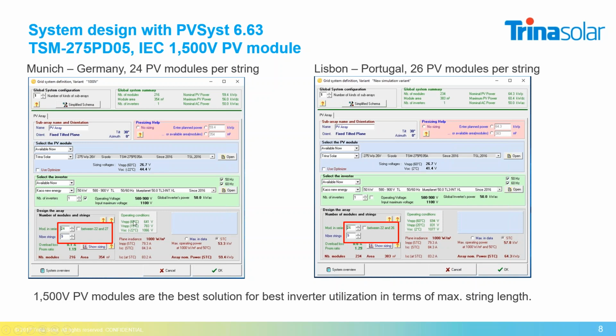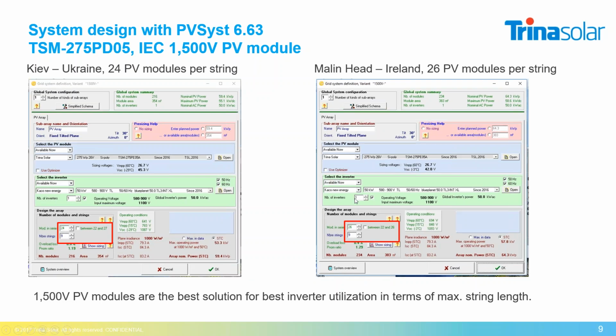And if I want to be below the 1100 volt, which is the limit of the inverter, you can see that I can select 24, and I already have 2 modules more per string than in the case before. If I go to Lisbon, I go from 24 up to 26 modules, which is also an increase of 2 modules per string, and a better utilization of the inverter. If I go to Kiev, it's also 2 modules more per string, so I go from 22 to 24. And if I look at Malin Head, due to the temperature you can expect, you have the biggest advantage, because you can go from 23 up to 26. That means you have 3 modules in addition per string.